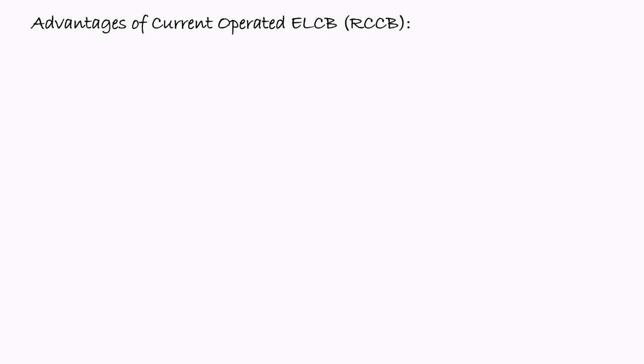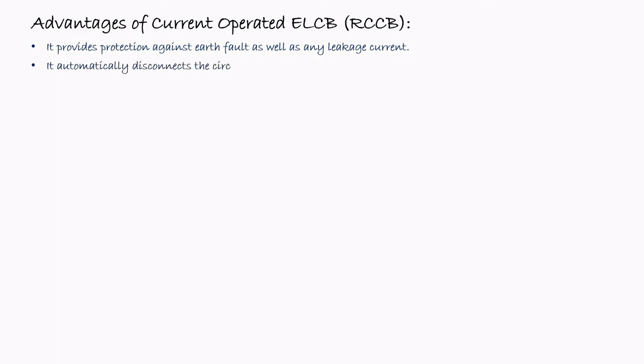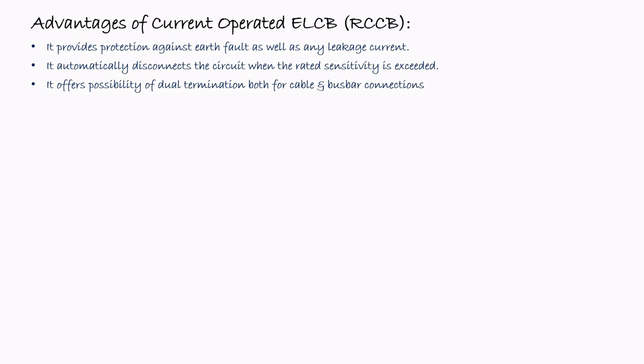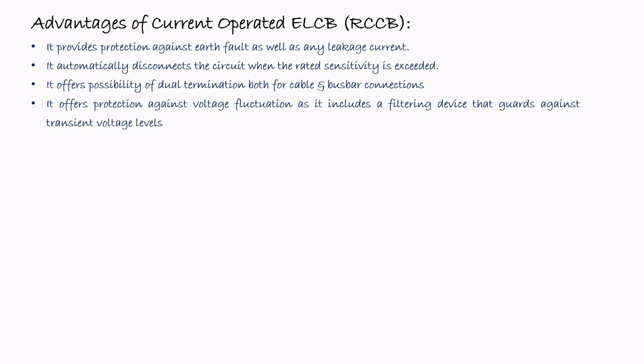Now the advantages of the RCCB or the current operated ELCB. It provides protection against the earth fault as well as any other leakage current. It automatically disconnects the circuit when the rated sensitivity is exceeded. It offers the possibility of dual termination both for cable as well as busbar connection. It offers protection against voltage fluctuation as it includes a filtering device that guards against the transient voltage level.